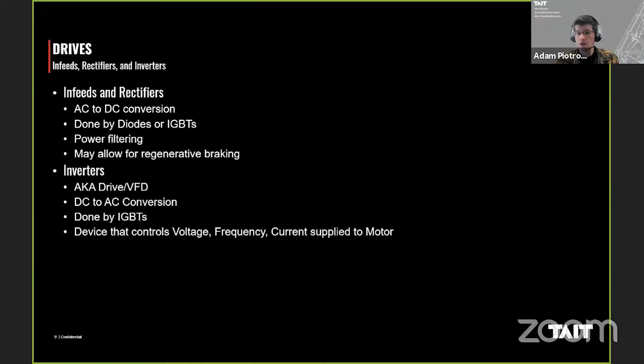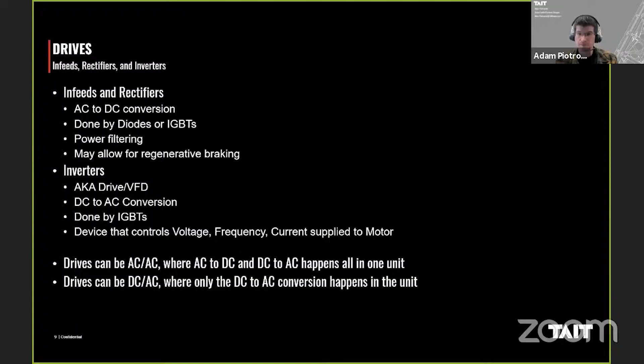And so drives can be AC-AC, where the AC to DC and the DC to AC happens all in one unit, or there can be separated units where a drive is just the DC to AC portion. So it's just the inverter stage, and then the AC to DC happens in a rectifier stage. This is important when it comes to component selection for us. TAIT uses a couple different manufacturers when it comes to drives, as well as PLCs. Depending on the application, we may decide to go with an AC-AC drive, where it's all packaged in one unit, or we may decide to break it out into a more modular or scalable system where the drive is just the DC-AC stage, and we have to add in an inverter, a rectifier, or an in-feed.